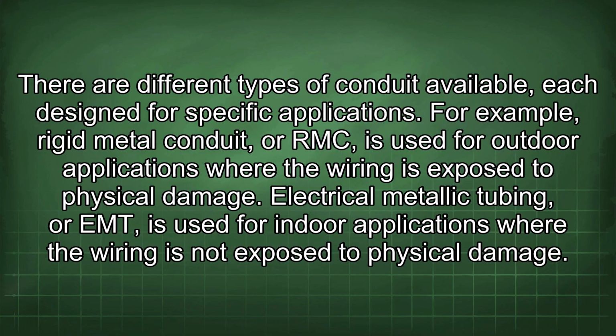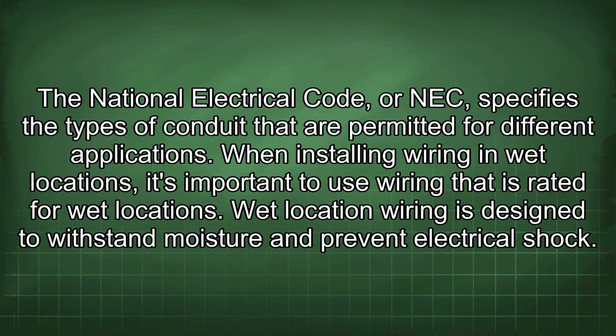For example, rigid metal conduit, or RMC, is used for outdoor applications where the wiring is exposed to physical damage. Electrical metallic tubing, or EMT, is used for indoor applications where the wiring is not exposed to physical damage. The National Electrical Code, or NEC, specifies the types of conduit that are permitted for different applications.